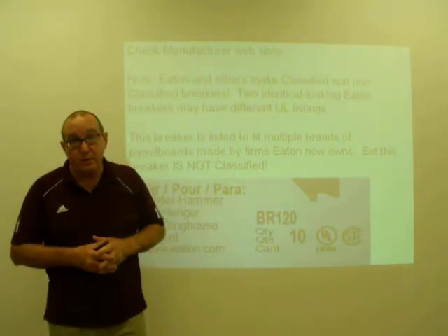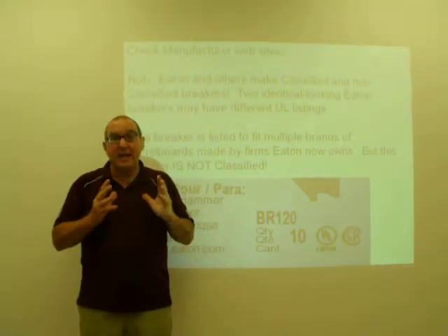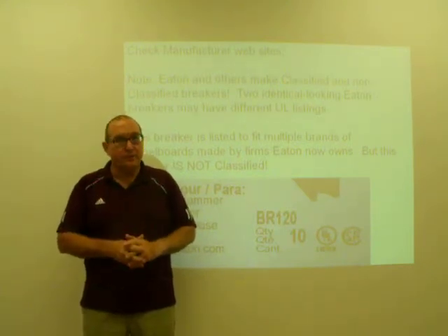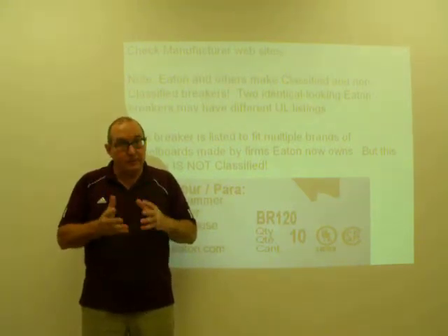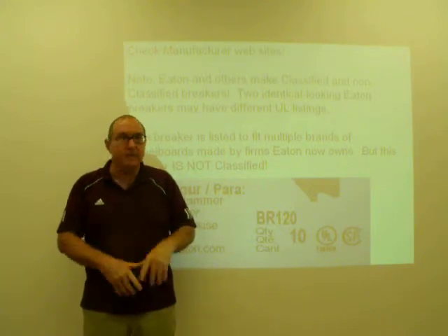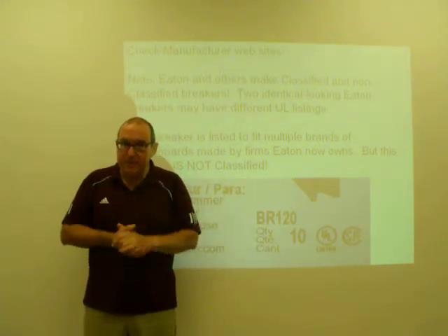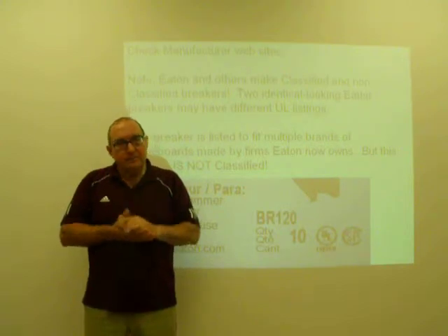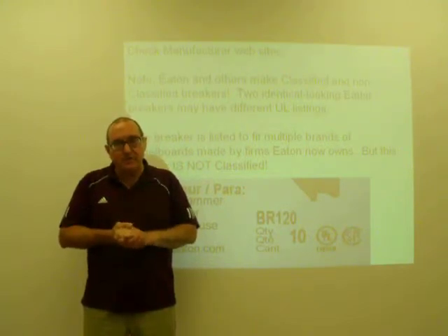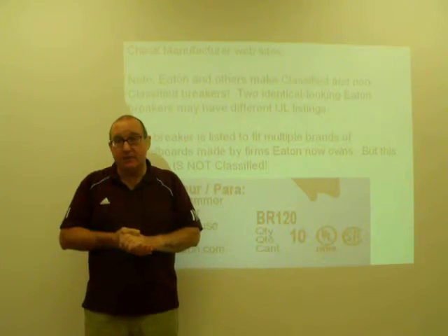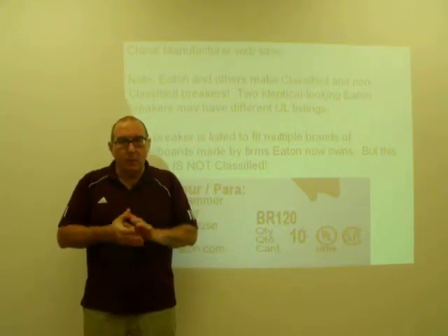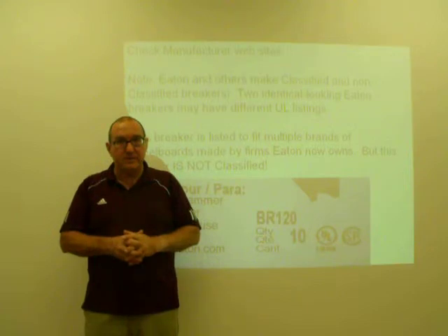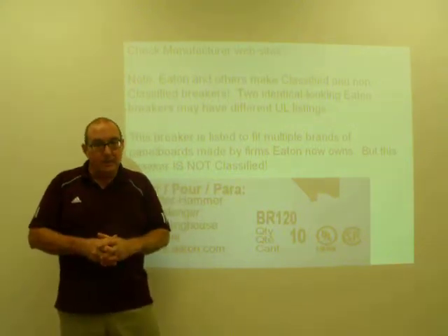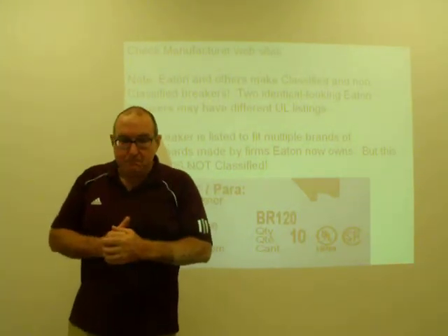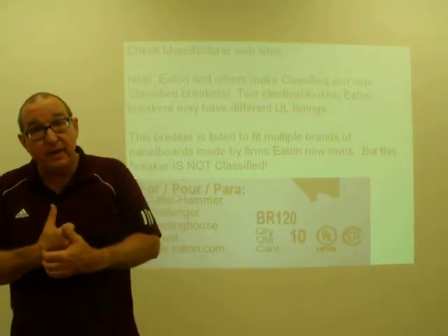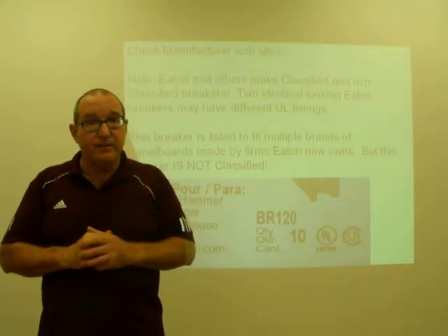You can check the manufacturer's websites and see what they have to say about what breakers are listed for use in their panels. Typically, if you're going to the Square D website, it's going to say you must use Square D breakers. You go to the GE website, it's going to say you must use GE breakers, and so forth. So what you may want to do is a web search for classified breakers or classified replacement breakers, and you'll come up with a wealth of information, a lot of blogs and so forth discussing the pros and cons of doing this. Now, there are some companies such as Eaton, Siemens is another one, that make classified breakers that are UL listed for other brands of panels.